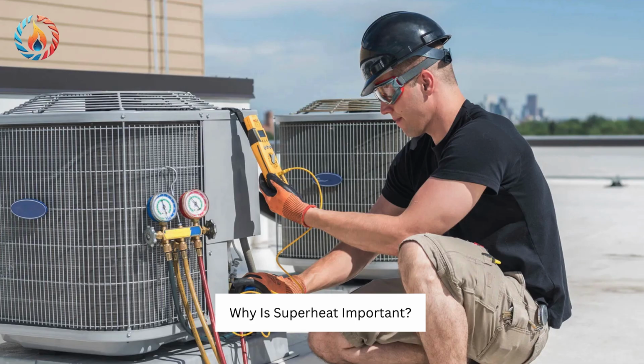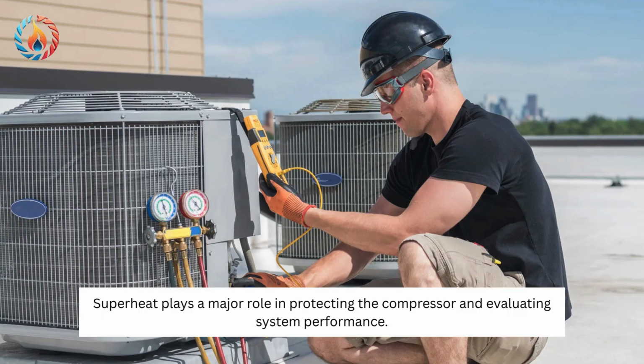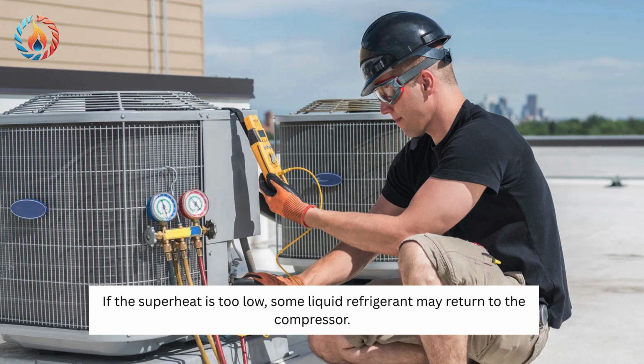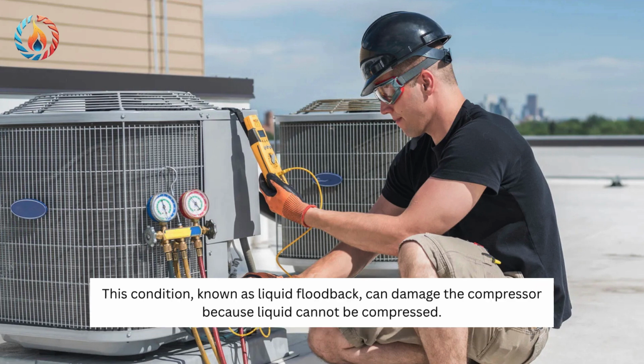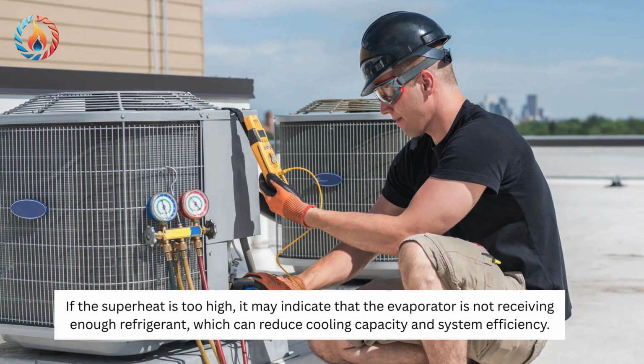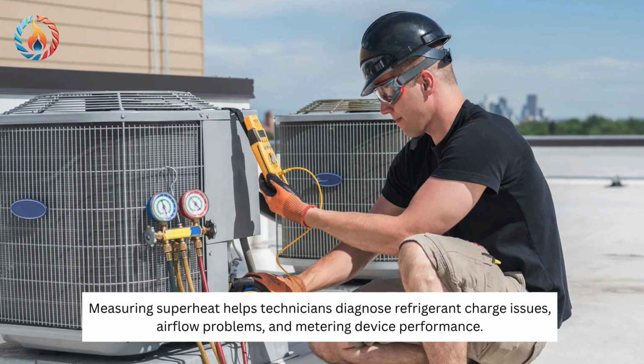Why is superheat important? Superheat plays a major role in protecting the compressor and evaluating system performance. If the superheat is too low, some liquid refrigerant may return to the compressor. This condition, known as liquid floodback, can damage the compressor because liquid cannot be compressed. If the superheat is too high, it may indicate that the evaporator is not receiving enough refrigerant, which can reduce cooling capacity and system efficiency. Measuring superheat helps technicians diagnose refrigerant charge issues, airflow problems, and metering device performance.